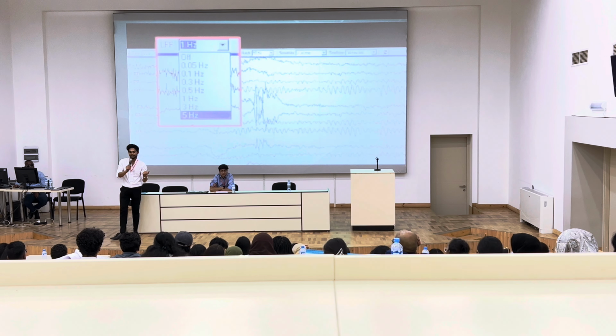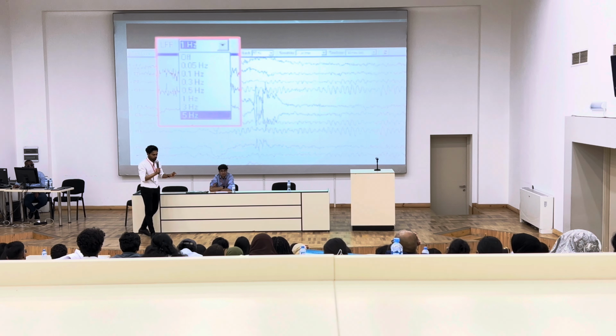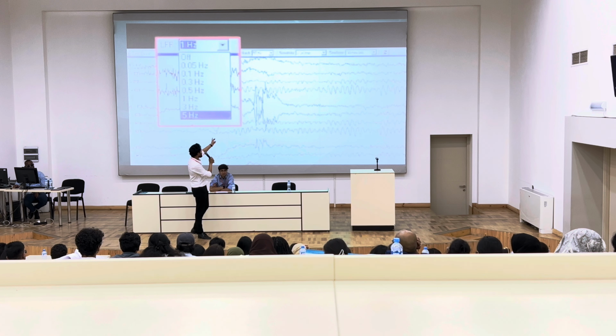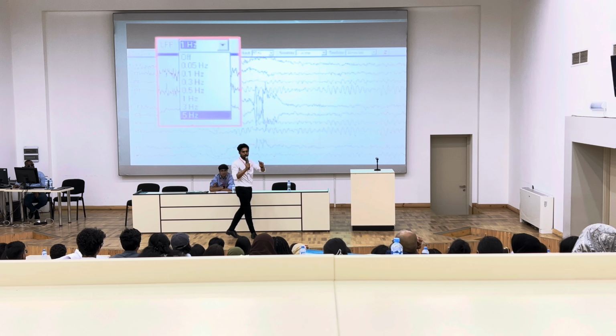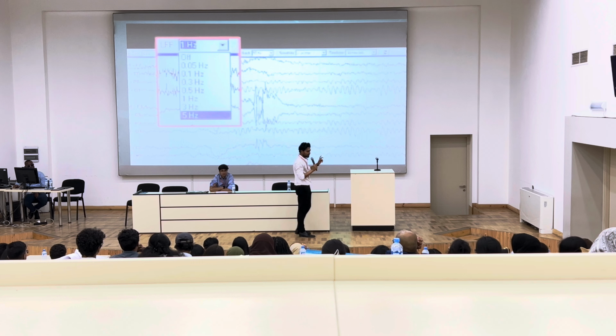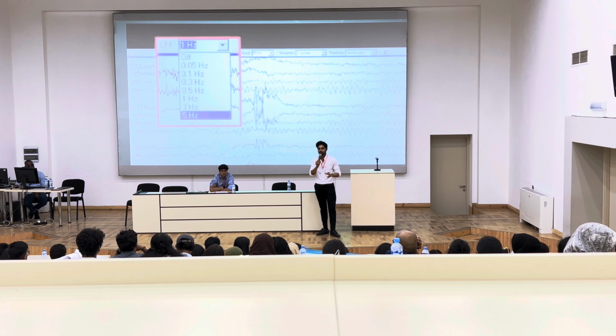Use the whole reading. Even though he doesn't have a seizure, it will look like a seizure. So this is what an EEG technician does. He has a bunch of filters on the top and he can play with it. So for example, the high frequency filter. Generally in most hospitals you set it at 70 Hertz.